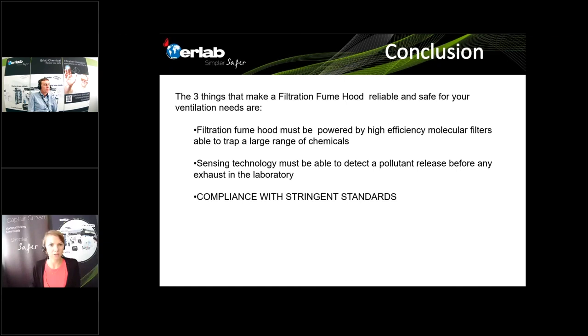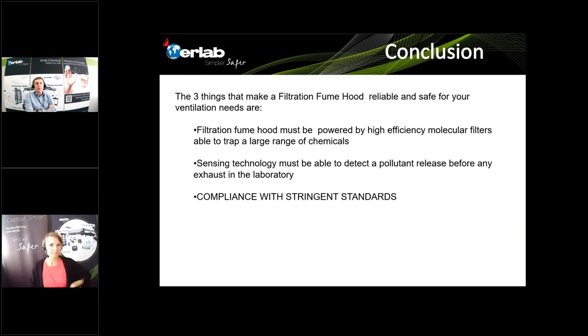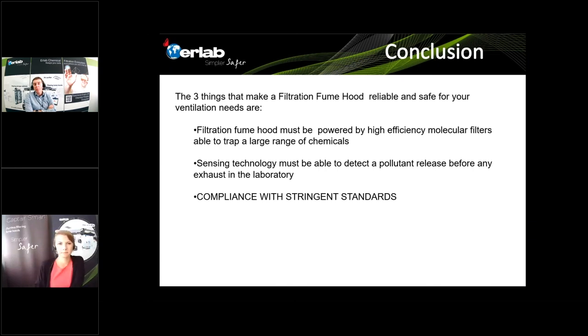Question: When do you recommend the ductless fume hood versus the ducted fume hood — how to choose? I would say first: it is not one against the other. You have a toolbox and you need all the tools collaborating together. Only a risk assessment can truly tell you what to use. If you have large amounts of solvents, you need ducted fume hoods for sure. If you cannot control your evaporation at all, you need ducted. But if you need protection at every square meter of your laboratory, I clearly recommend also having filtered or recirculatory fume cupboards. Risk assessment is the starting point.